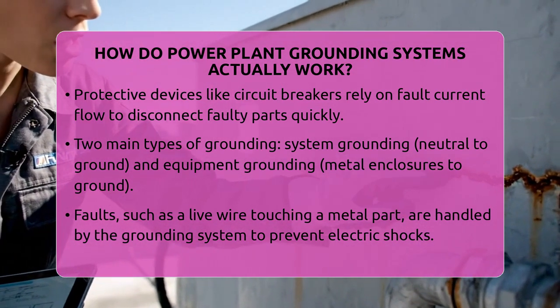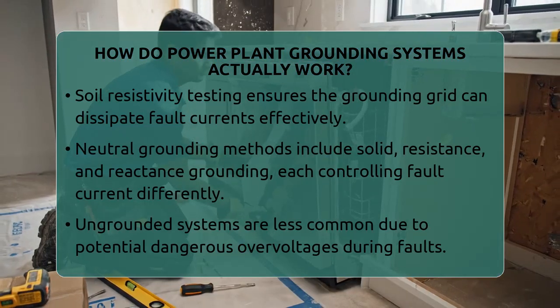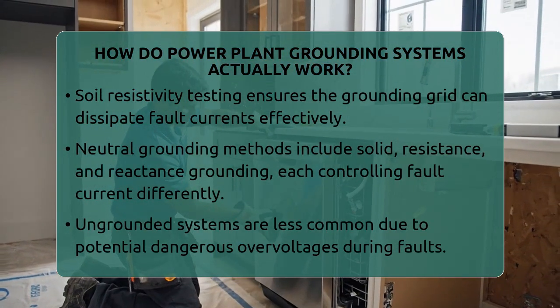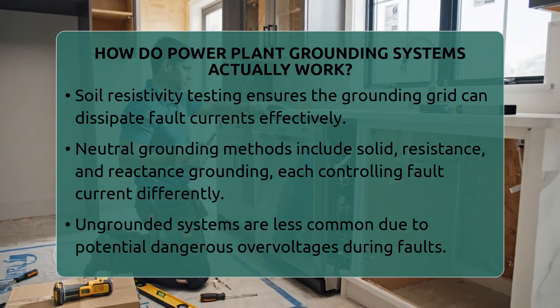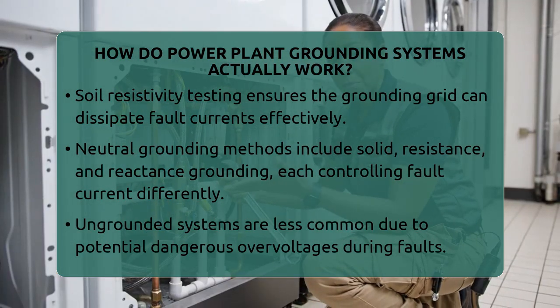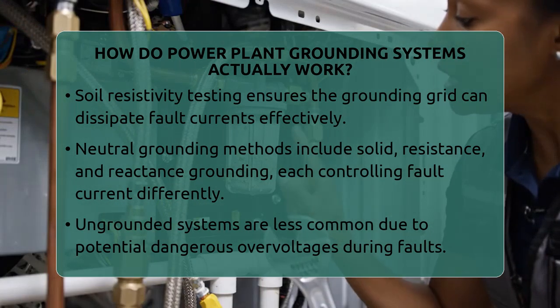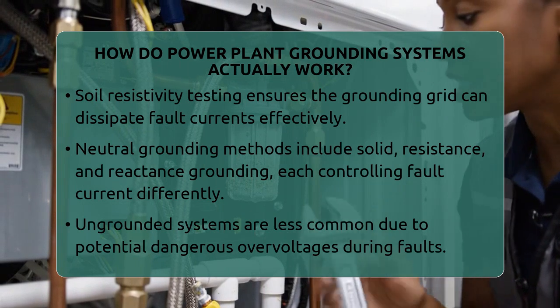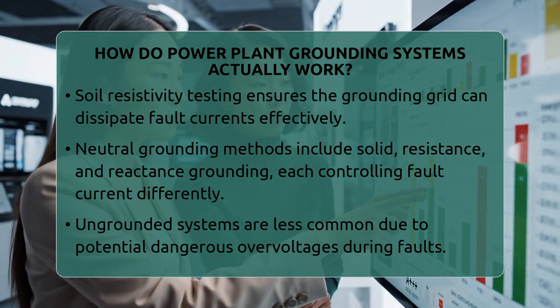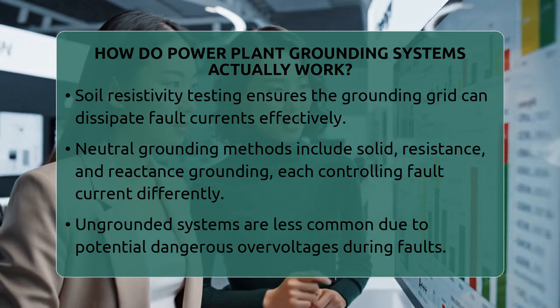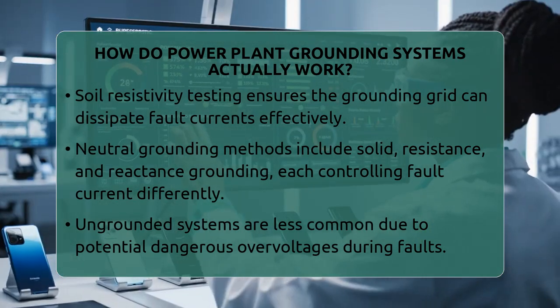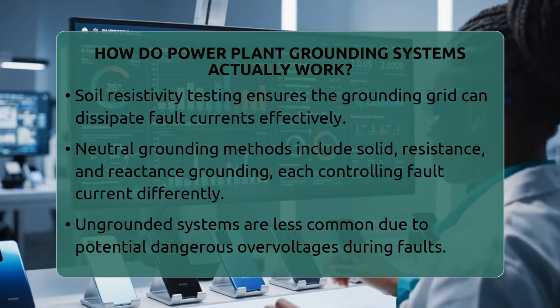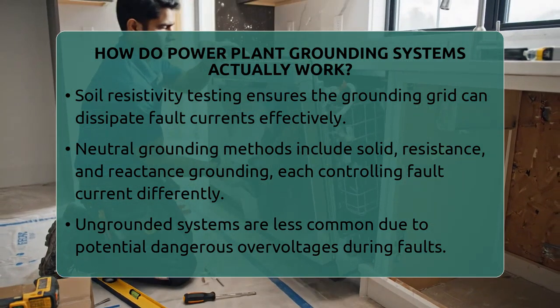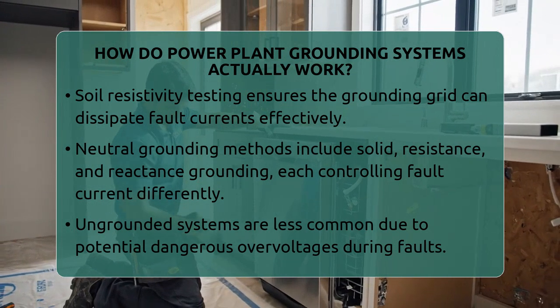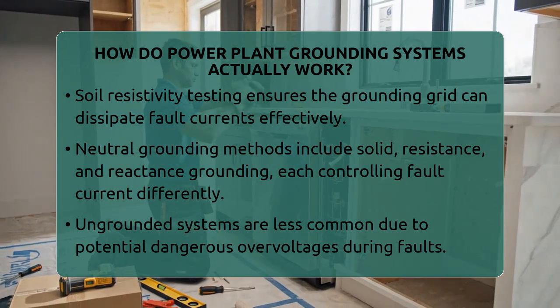Neutral grounding methods influence how the system reacts to faults. Solid grounding connects the neutral directly to earth without any resistance, allowing large fault currents that are easy to detect. Resistance grounding adds a resistor between the neutral and ground, limiting fault current and reducing stress on equipment. Reactance grounding uses an inductor instead of a resistor, helping control transient overvoltages. Ungrounded systems do not intentionally connect the neutral to earth, but they can develop dangerous overvoltages during faults, so they are less common today. Designing a grounding system involves considering voltage levels, soil conditions, and safety standards.